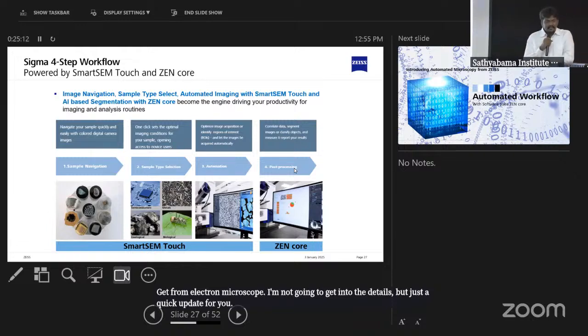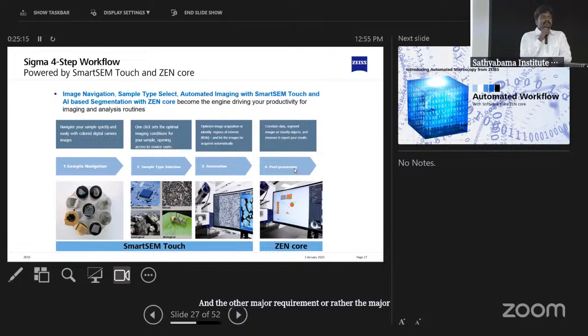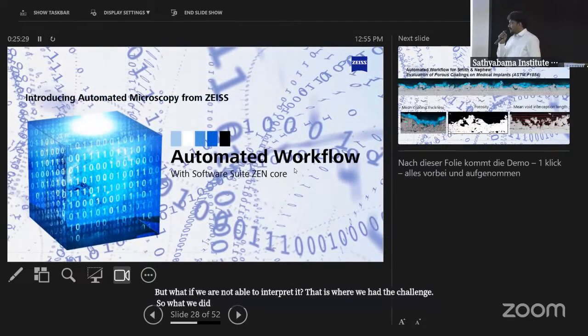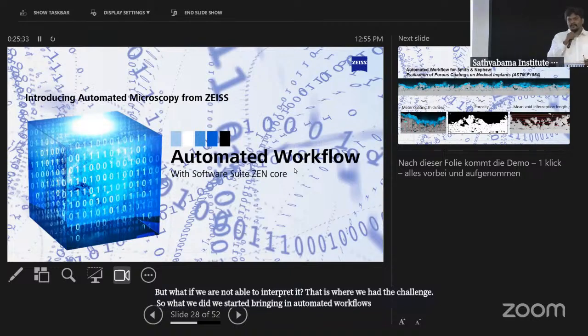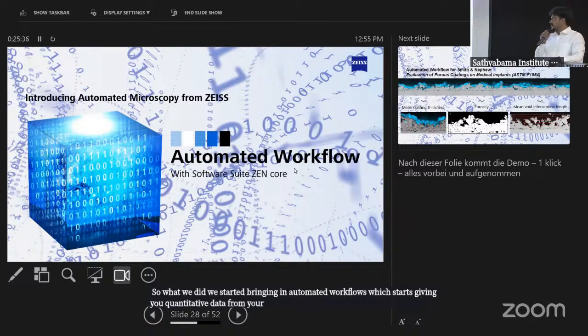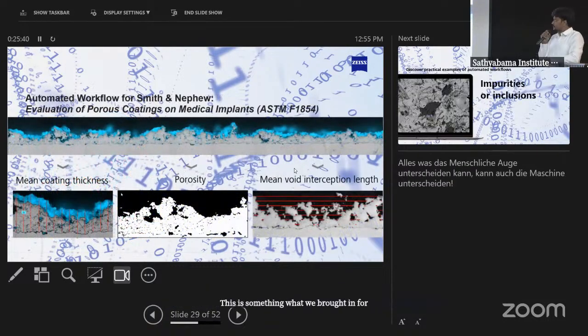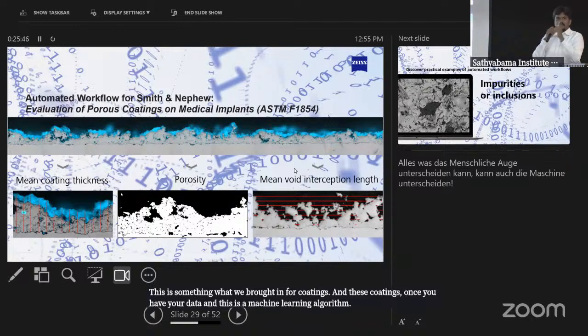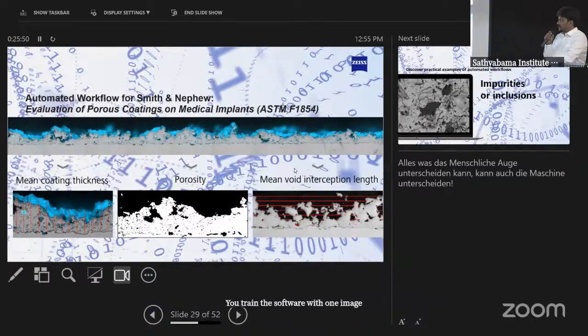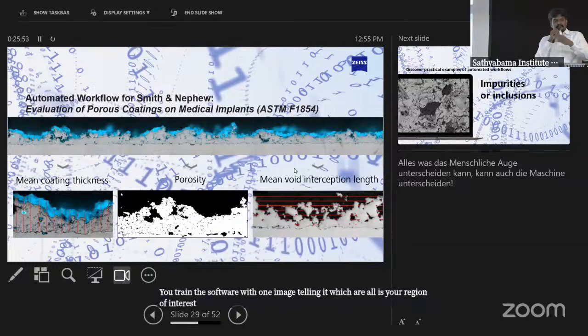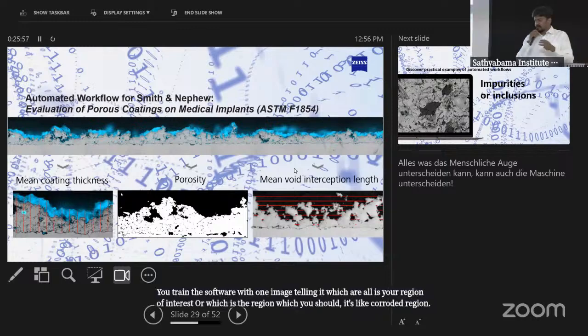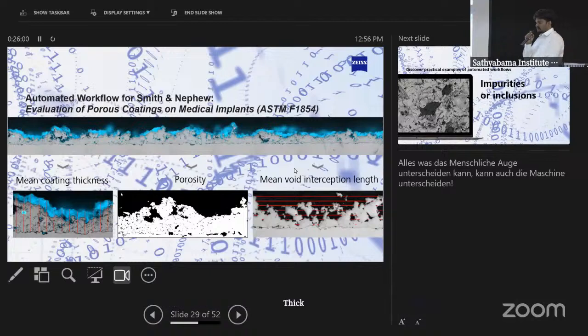And the other major requirement, or rather the major challenge, is interpretation of data. I mean, we can capture beautiful images or beautiful data from your samples, but what if we are not able to interpret it? That is where we had the challenge. So we started bringing in automated workflows, which start giving you quantitative data from your sample as well. For instance, this is something we brought in for coatings. This is a machine learning algorithm: you train the software with one image, telling it which is your region of interest, or which is the corroded region. You train the software, and it could be for corrosion, or thickness, or porosity, it could be for anything.